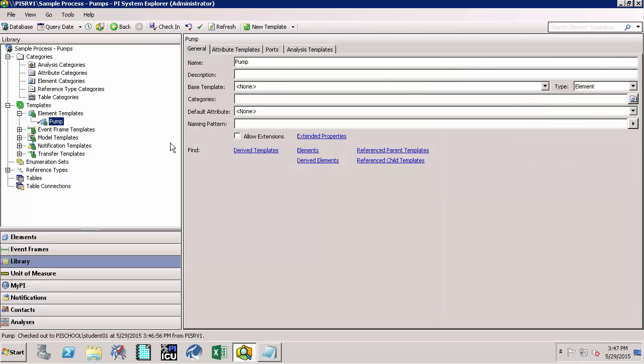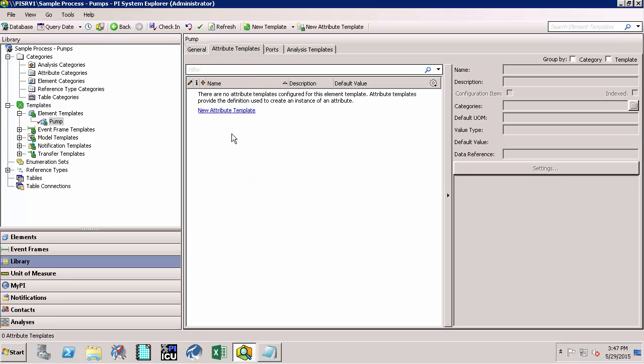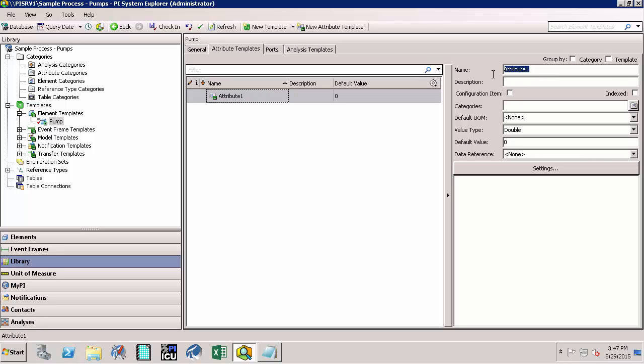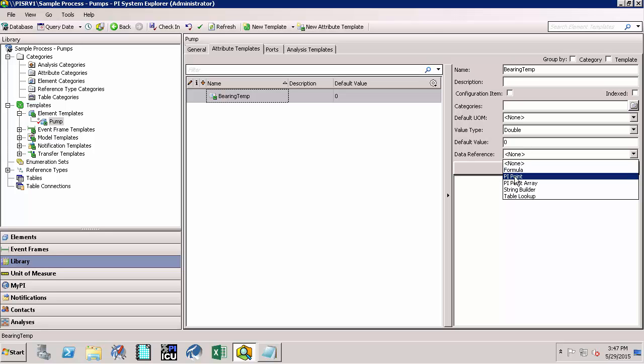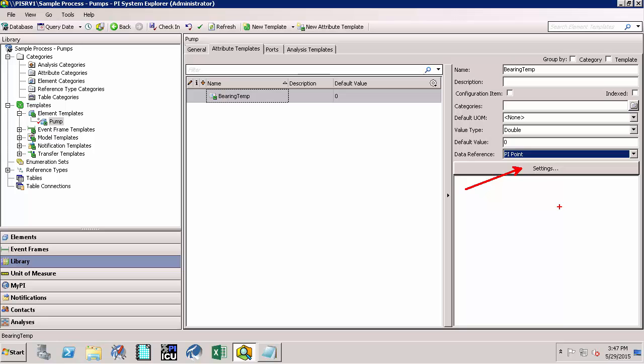Now let's say OK and minimize this, and go back to PI SRV1. Once we are on PI SRV1, let's get back to PI System Explorer which we had minimized earlier. Now let's define a few attributes for the pump. To do that, let's click on the Attributes Template and click on the New Attribute Template link. Let's define the name for this attribute as 'BearingTemp' with a capital B and capital T, no space. From the Data Reference drop-down, select PI Point, then click on Settings to define the attributes for the PI Point.